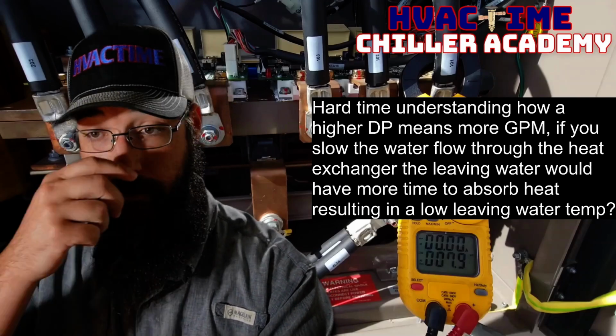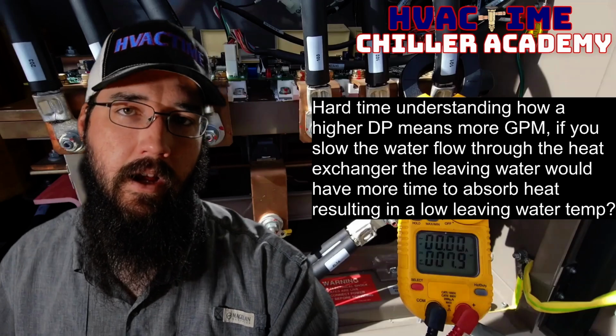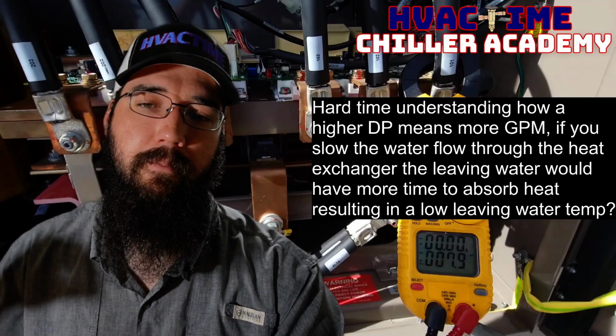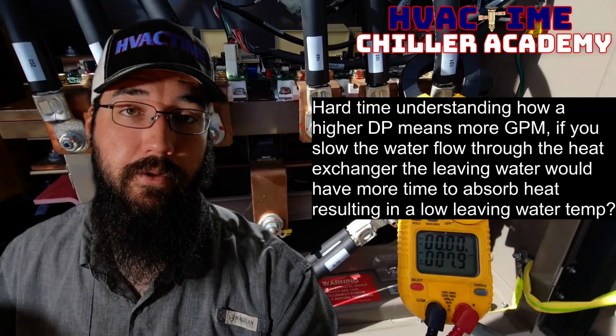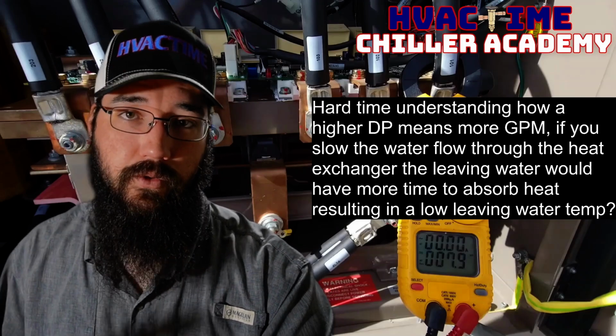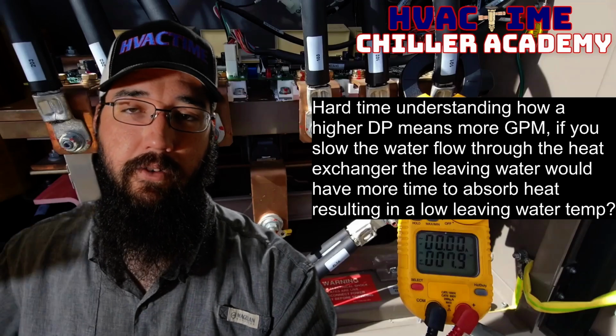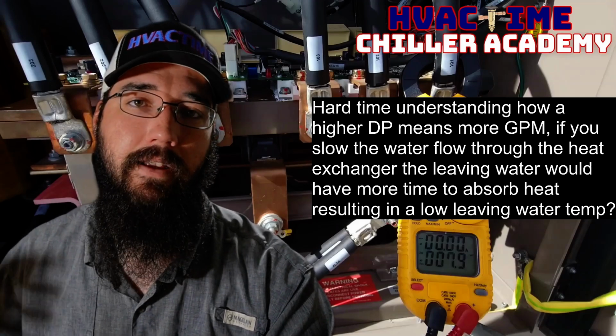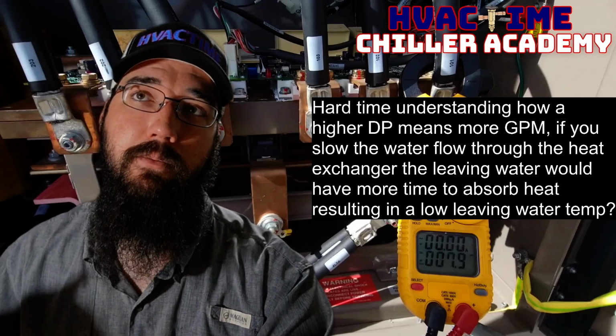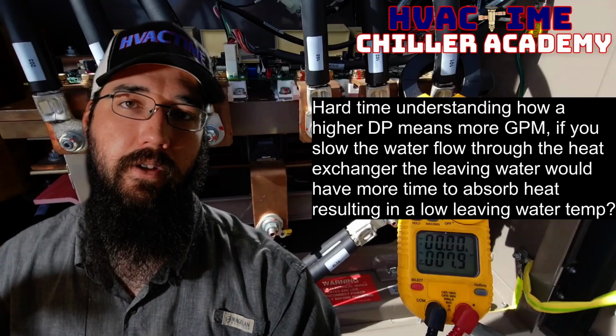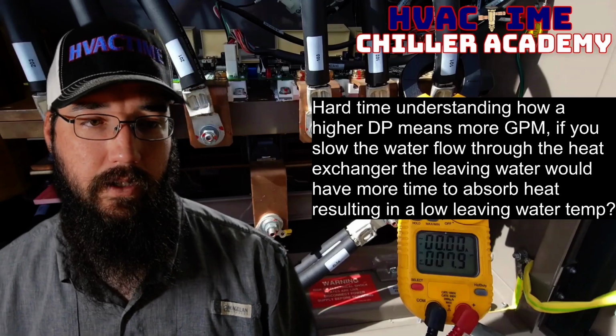The big core concept there is getting a grasp that higher differential across the heat exchanger, you know, evaporator, condenser, either or, does mean a higher GPM. And that will influence our temperature differential. Those do have a correlation, because how fast the water moves does impact how much approach is needed to achieve the rate of heat exchange that we need to be successful.